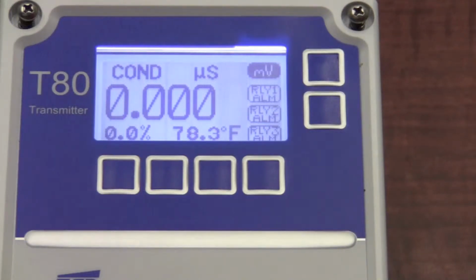The T80 can be purchased as a 2-wire loop-powered unit. It can be also line-powered. When I say line-powered, it could be AC or DC, and can have relays. When I do buy a line-powered unit, I do get the backlighting on the display. It is an LCD display, which is very good in high-intensity light areas, as in outdoors. There's also a sun shield available for the T80.